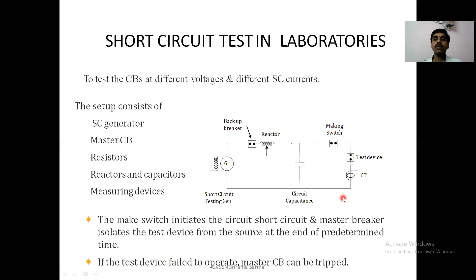Before going to the short circuit testing procedure, let us see what equipment is used in the short circuit testing stations. You can observe a circuit here: a generator driven by a motor, a master breaker, make switch, the inductance and resistance of the circuit, and a short circuit transformer and test breaker, which we can represent like this. This is the reactance of the short circuit generator, master circuit breaker, making switch, reactance, short circuit transformer, resistance and capacitances, circuit breaker and test.